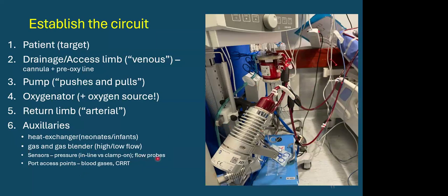Probably the most important part of the circuit is the flow probe. The flow probe is this structure here, and that's on the return limb, and that'll tell you what the effect of your cannulas, your volume status, and your speed is, and what's ultimately returning to the patient.